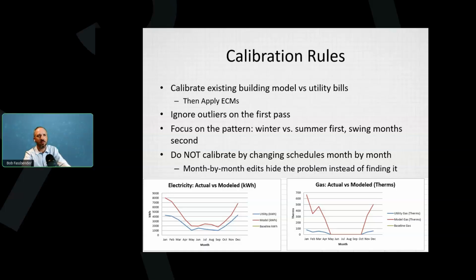The main thing here is you focus on winter before summer. In this case, we have electric and gas. And I don't know anyone's experience with modeling here if they could guess what was wrong. But one thing you do not want to do is you do not want to start changing the schedules month by month to fix it, because that's not the problem. You want to get the shape as close as possible using standard assumptions, actually using as few inputs as you can, and get those to match closely. And then sometimes you have to calibrate a month. Anyway, in this case, I don't know.